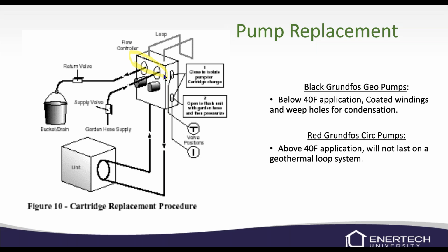You can put a cam adapter or some kind of adapter in that flush port, and you can drain that into a drain. So basically, you're going to lose the fluid, if there's shutoff valves here on the side of the flow center, that's going to isolate the loop. So then you just have this small standing column of water there, and then you'll just have a little bit of water before these little black pumps that are listed there. So you can drain a little bit of water out, and then you can pop off the pump and take that pump out.